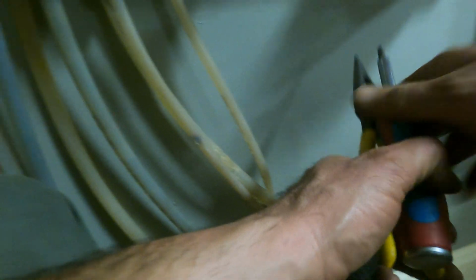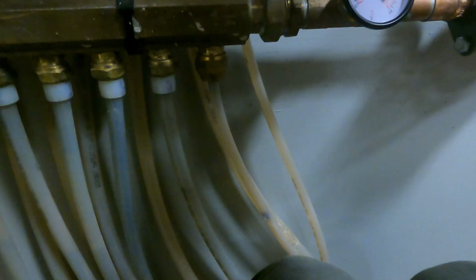There's 2 actuators that need to be replaced because the stuff that locks it on, that little clip, I guess, snapped off in there. It goes around the ring. It's like one side of it isn't clipping in. One side you can't get down. So it won't push down the valve. So the actuator's probably gonna have to be replaced there.